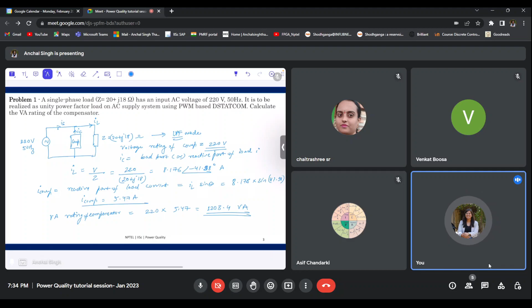So this I compensator will come out to be 5.47 amperes. Therefore, my VA rating of compensator is equals to VA is voltage into current, 5.47, which comes out to be 1203.4 volt amperes. Wasn't this easy? Just try to understand what is the purpose of the compensator: to supply the bad part of load current, okay, or the reactive part. So whenever you start from that, step automatically flows. Just focus on what you have to calculate and what is the purpose of the compensator. That's it. Let us move on to the second problem.